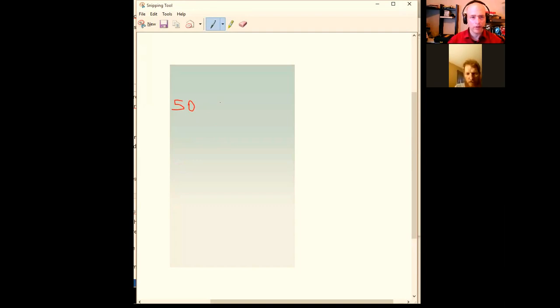So 50 is all that I care about. I don't really care about the amperage rating. Plus there's 4 in each of the 10 offices that they give you, and so 4 in each of the 10 offices gives you an additional 40. That gives us 90 so far. And then there's 4 in each of the 4 restrooms, which is another 16. And then we've got 4 in a break room. And so ultimately you're looking at 50 plus 40 plus 16 plus 4, which gives you 120, I think, right? 90, 106, 110 actually. 50 plus 40 plus 16, yeah, 110. I got 110.